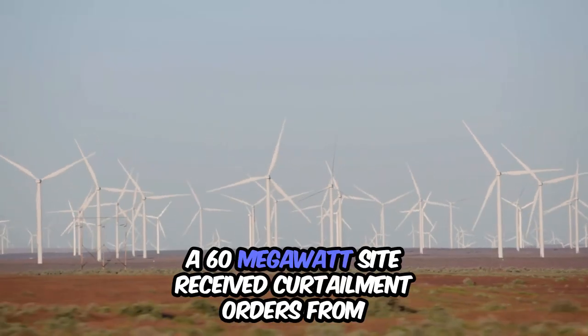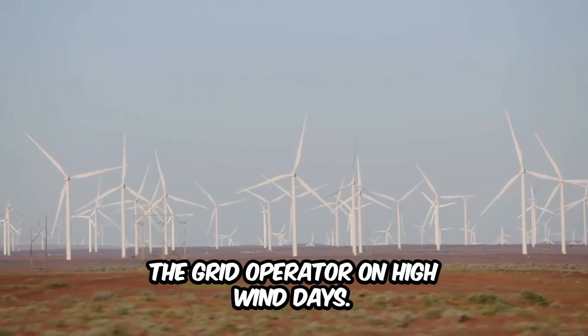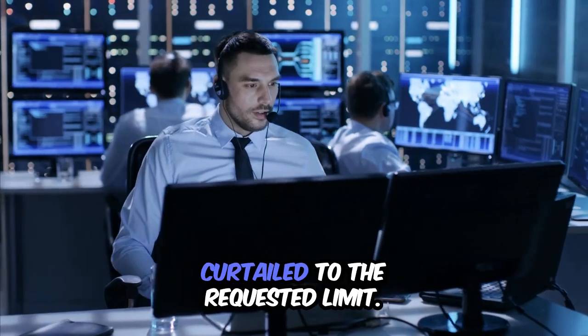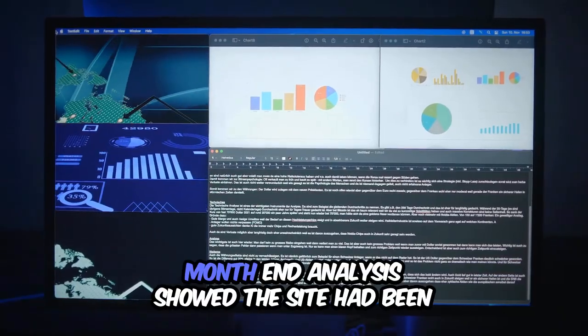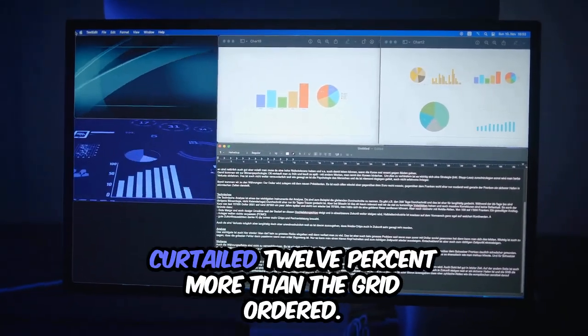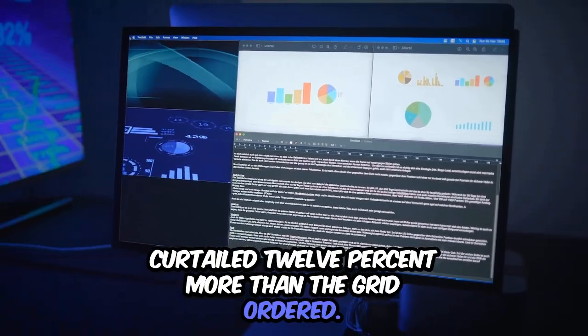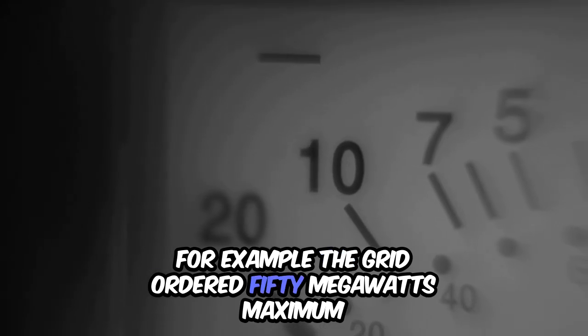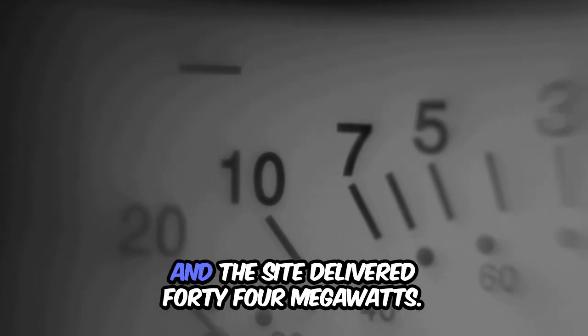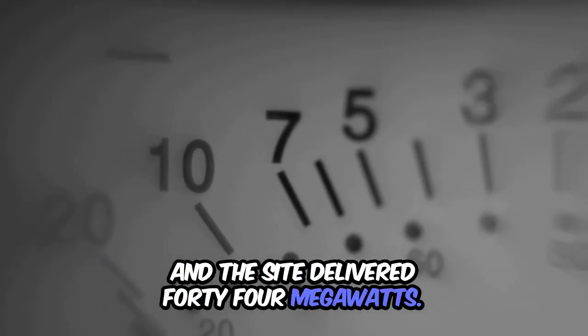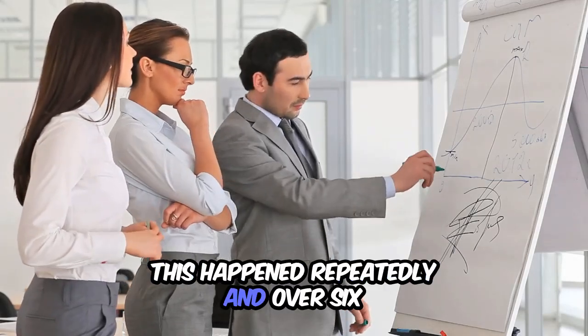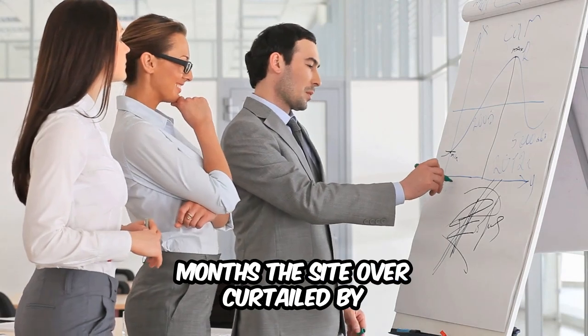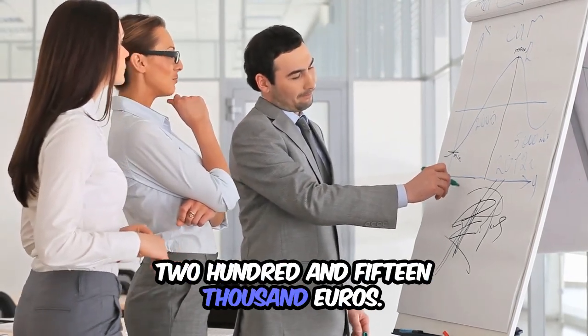A 60 megawatt site received curtailment orders from the grid operator on high wind days. The operator complied immediately and curtailed to the requested limit. Month-end analysis showed the site had been curtailed 12% more than the grid ordered. For example, the grid ordered 50 megawatts maximum, and the site delivered 44 megawatts. This happened repeatedly, and over 6 months, the site lost 215,000 euros.